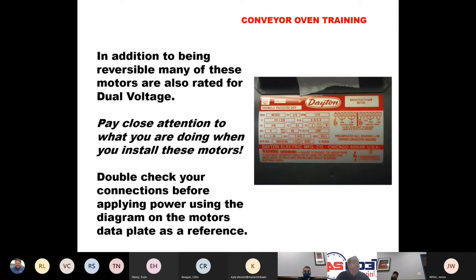In addition to being reversible, a lot of these are dual voltage. So you want to pay close attention to what you're doing when you're installing them. Always double check your connections before you apply power, using the diagram on the motor data plate as a reference. Also, always make sure you know what your input voltage to that motor is before you start wiring the motor.